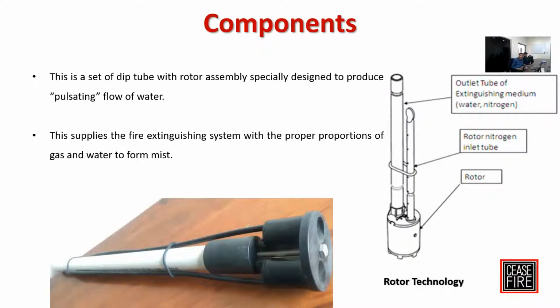This is the major component. Again, a patented rotor technology with us, where you can see the dip tube at the end is fitted with the multi-rotor, and this rotor has small fans inside. When the pressure starts from the top of the cylinder, these fans start rotating. Once they move, they mix the nitrogen and the water together and create a bubble effect. Once the bubbling effect is created, the conversion to water mist becomes very easy. That's where at a very low pressure, at 15 bars, we are able to achieve less than 60 micron size of water mist. Because of this technology only we can do it. Otherwise, in the industry, anyone who wants to create a water mist uses high pressure technology. With low pressure, they cannot achieve this size of water mist particle.